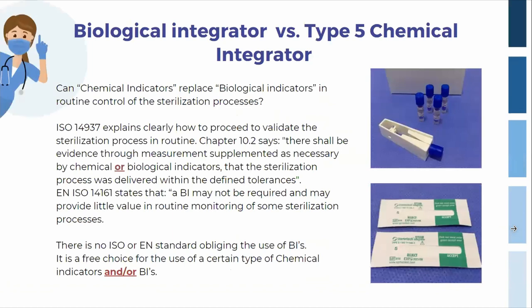So can biological indicators replace chemical indicators, or chemical indicators replace biological indicators, is the question most people ask. ISO 17665 clearly explains how to proceed to validate the sterilization process and routine monitoring. Chapter 10.2 says there shall be evidence through measurement, supplemented as necessary by chemical or biological indicators, that the sterilization process was delivered within the defined tolerance. There is no ISO or EN standard obligating the BI use. The use of a certain type of chemical indicator and/or biological indicator is a free choice. The only mandatory test is the Bowie-Dick test.